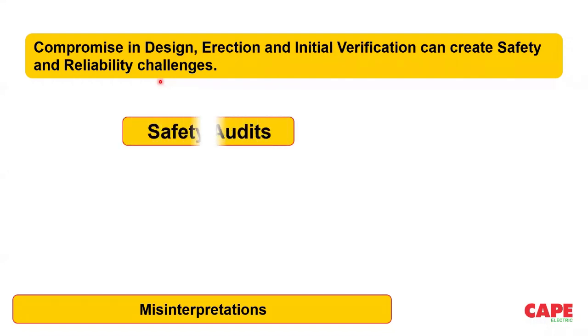Now, to enhance safety, what we do is safety audit. The word safety audit is very interesting to understand. Please note that audit is a checking, sample checking. Sample checking in the sense you have 100 circuits, you check 3 circuits on a sample basis and you make an audit, or you check 10 circuits and you make a safety audit. This actually is illegal as per the standard.